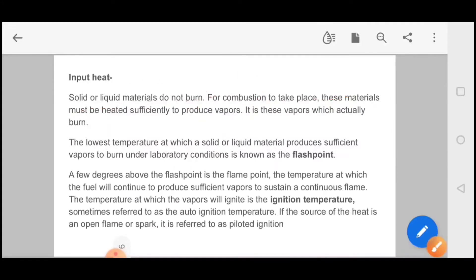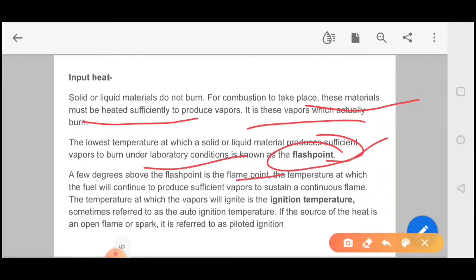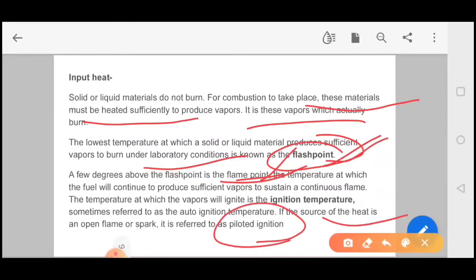For combustion to take place, materials must be heated sufficiently to produce vapor — it is the vapor which actually burns. The lowest temperature at which a solid or liquid material produces sufficient vapor to burn under laboratory conditions is known as the flash point. A few degrees above the flash point is called the flame point — where vapor continuously produces a flame. The temperature at which vapor ignites is the ignition temperature, also called auto-ignition temperature. If the heat source is an open flame or spark, it is referred to as piloted ignition.